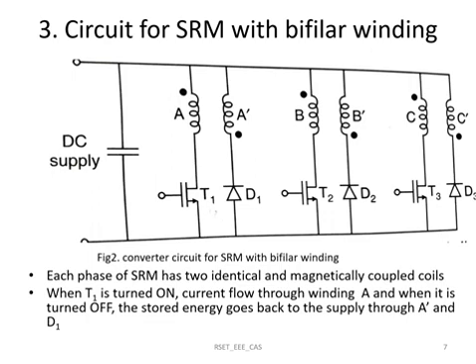The third converter circuit is for an SRM motor with bifilar winding. Bifilar winding is a winding which has two sections with a common terminal. For a particular phase the motor will have two identical and magnetically coupled coils A and A-dash, so each phase winding has two sections with one common terminal. If an SRM motor with bifilar winding is used, we can use this type of converter circuit.